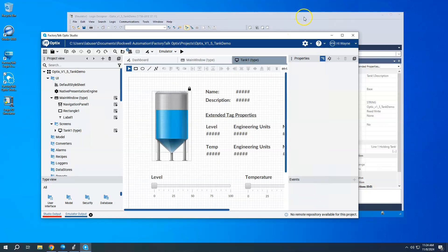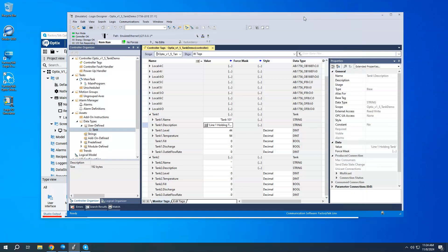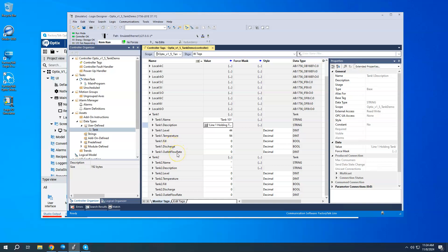Just to show what I've got set up, I have a really simple Logix application created and running in my Logix Echo emulator. Essentially, all it is is I've created a UDT, user-defined data type, that kind of has a structure. The premise is going to be like a tank. So I've got tank 1 UDT created and tank 2 UDT created. I just put a few tags underneath just to kind of show something. So I've got a couple of string tags such as name and description. I've got a level, a temperature, and a couple of Boolean points around a fill and discharge valve, perhaps. And then another integer or double integer value for outlet flow.